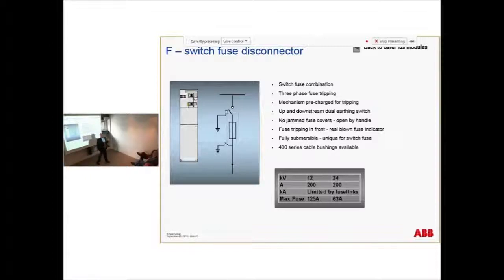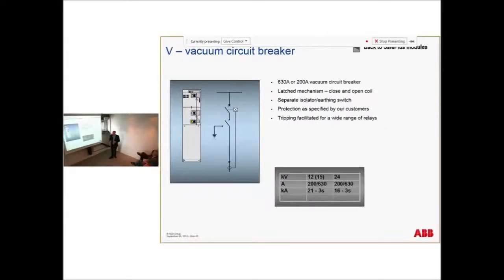So for design criteria, personal safety has been very important. The vacuum circuit breaker, this bottle is the same for all. It's called VD4. That's what they sell it as from Ratingen in Germany. And then we have the possibility to put a relay on it. I know you use a lot of this REF603 with the display, the self-powered.